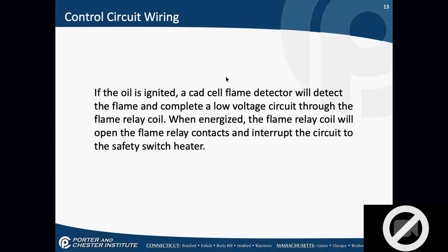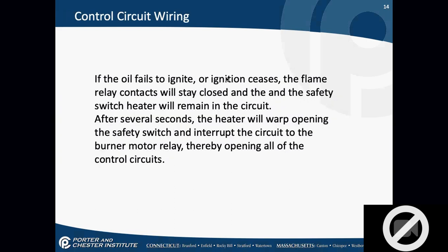The oil is ignited. The CAD cell flame detector that I just showed you, the yellow thing, will detect the flame and complete a low-voltage circuit through the flame relay coil. Okay? When energized, the flame relay coil will open the flame relay contacts and turns off what we call a safety switch heater, and I'm going to spend more time on this when we talk about the internal workings of the safeties. But it basically turns off a safety switch heater by bypassing it. If the oil fails to ignite or if the flame goes out, the flame relay contacts stay closed and the safety switch heater remains in the circuit.